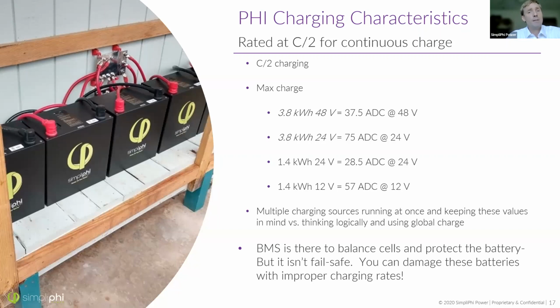So if you had 10 of these batteries in parallel, just in parallel, then you're looking at 375 amps DC at 48 volts. Keep those things in mind. It's a similar calculation for the 1.4, the 24 volts.